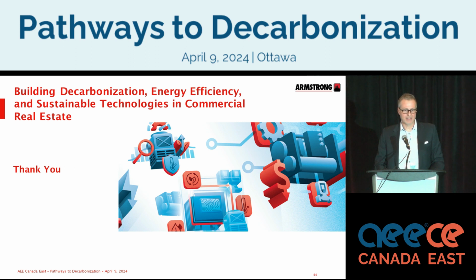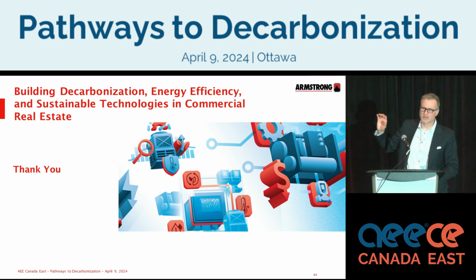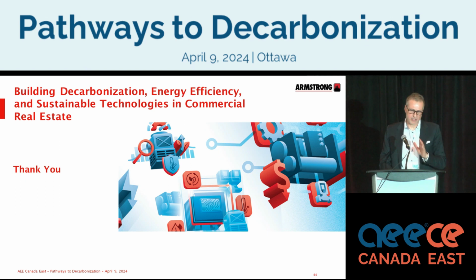But with that being said, I and a colleague are now working on 2 projects where it's a single chiller application and they're 400 tons. And the reason being is that, I'll throw the brand, they've got smart units in there, and they're 500 tons, and he's got 5 compressors on there. But the way they have it set up right now is that even at part load, the chiller is running at full capacity. So being able to collect the data set helps you identify. And so now it's not strictly on the chiller side, but there's the tower optimization opportunity and the chilled water side of the opportunity.